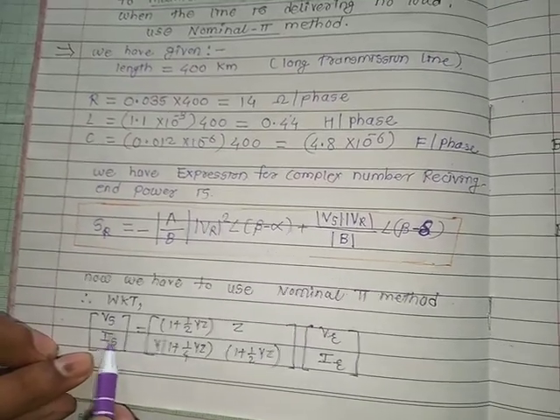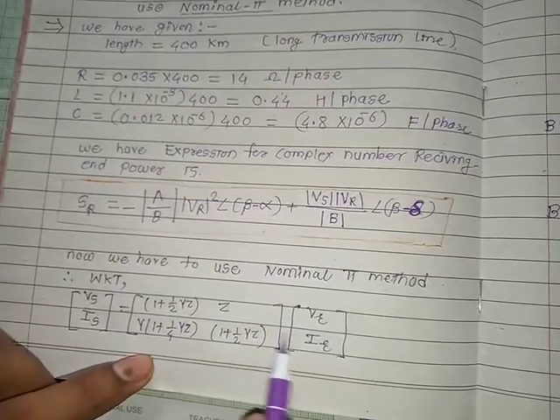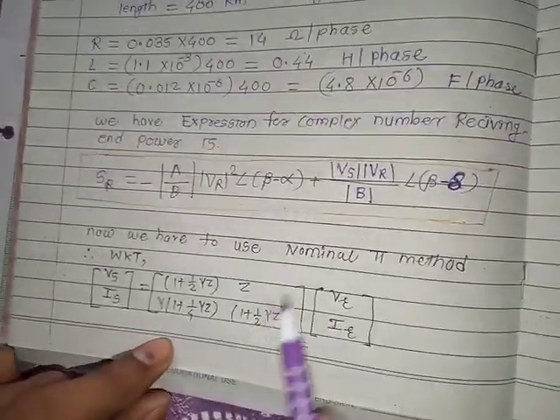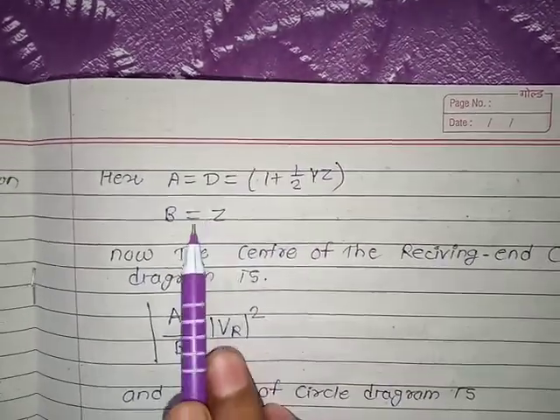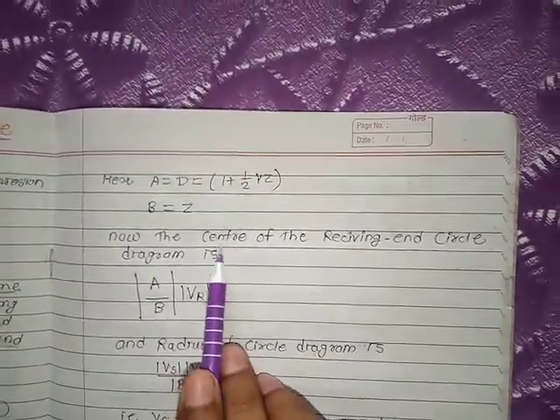For the nominal pi method, the ABCD parameters are: A = D = 1 + (1/2)YZ, and B = Z. Now we need to calculate the center of the receiving end circle diagram using the formula: center = (|A|/|B|) × Vr² at an angle β − α.